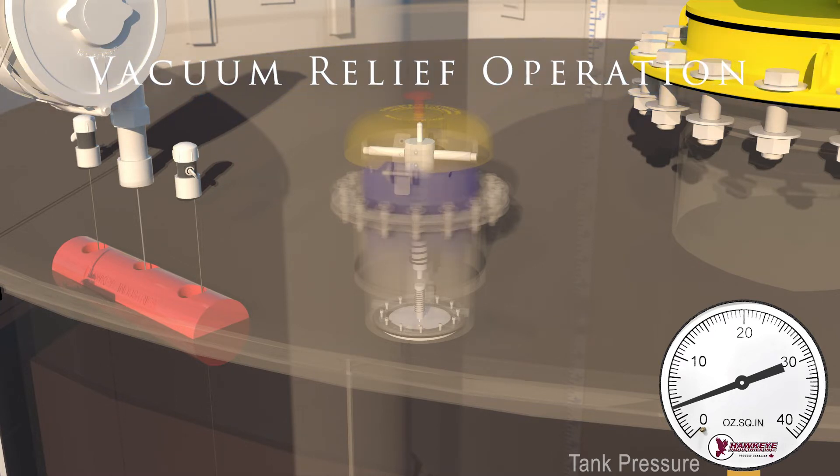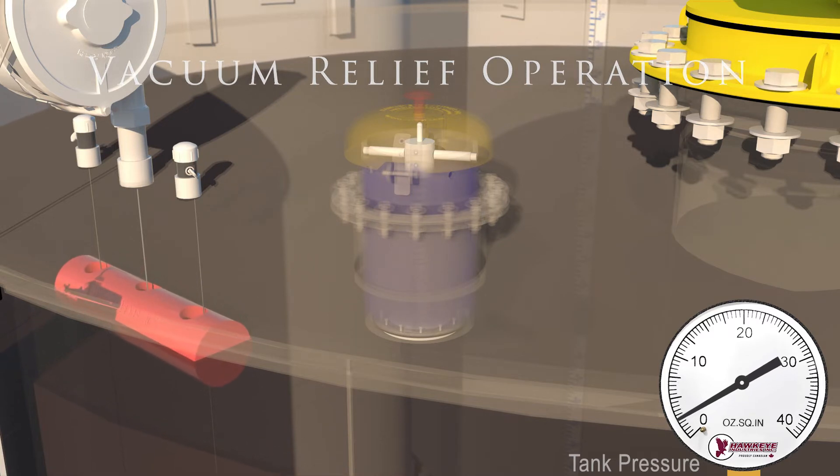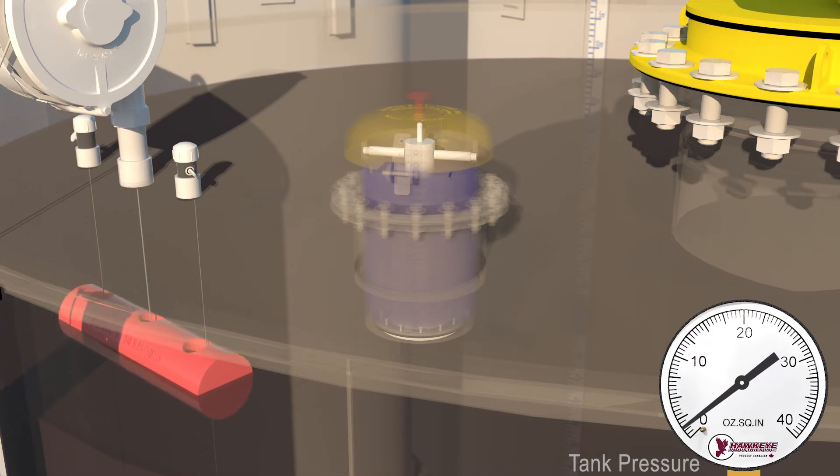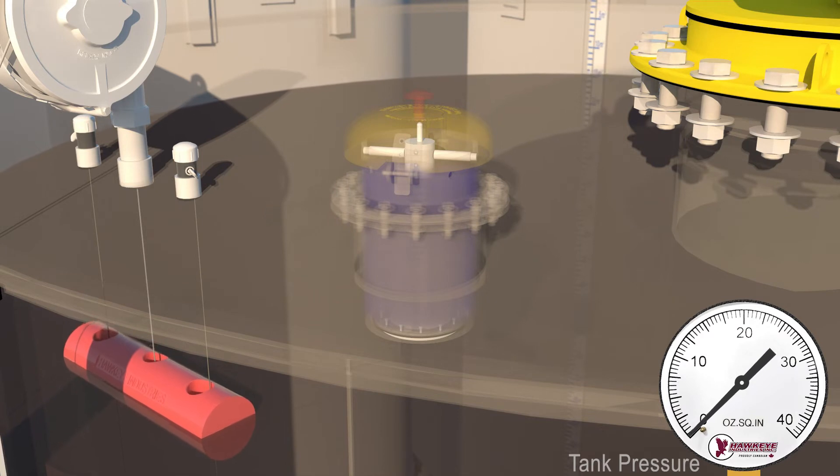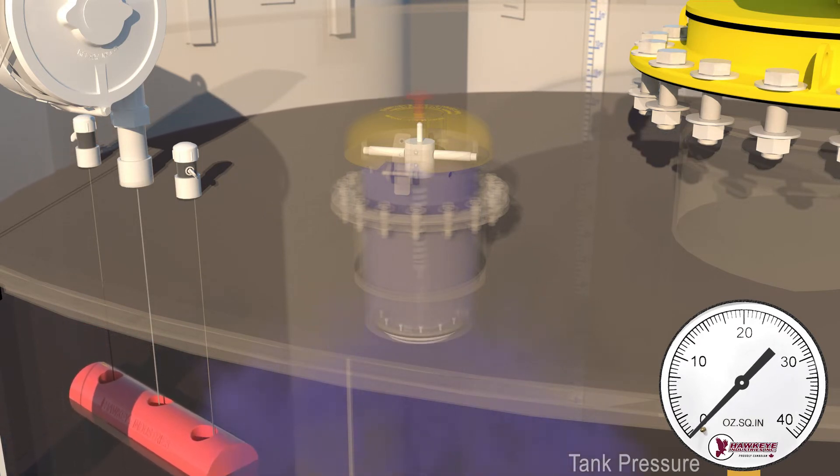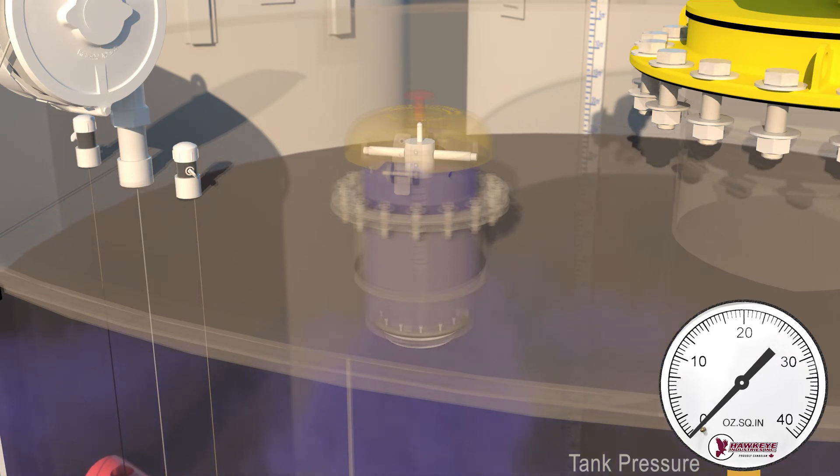As the fluid leaves the tank, the internal pressure decreases below atmospheric, leaving the tank at risk of collapse. When the tank pressure drops below atmospheric pressure by 0.4 ounces per square inch, the vacuum pallet opens and allows atmospheric air to enter the tank.